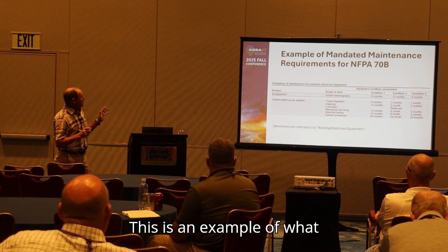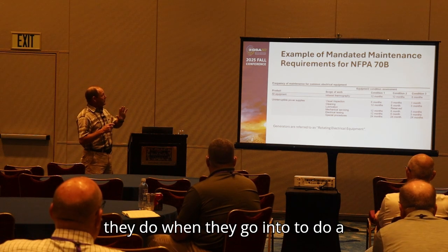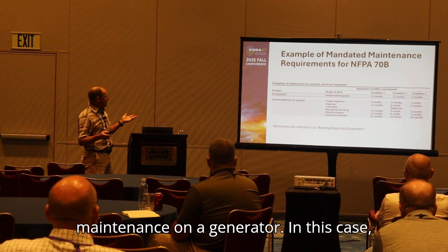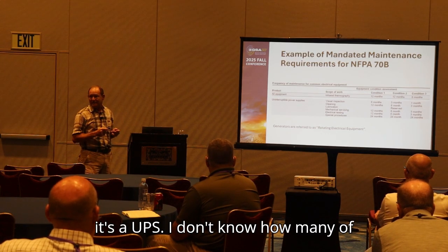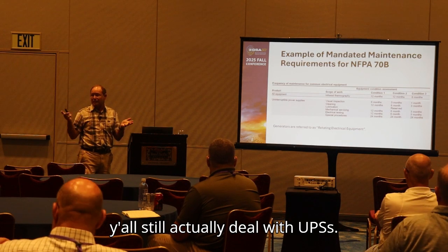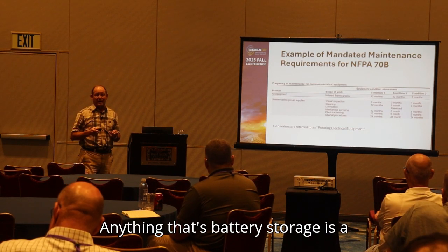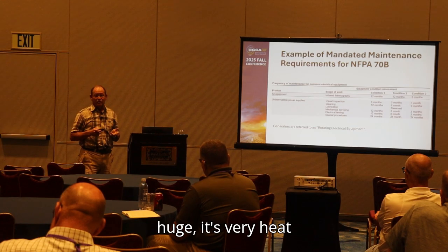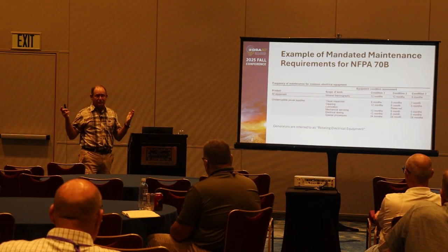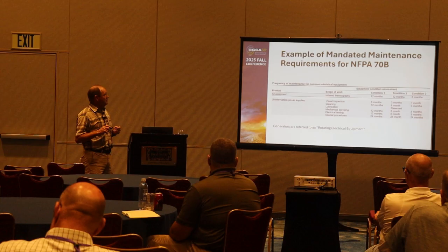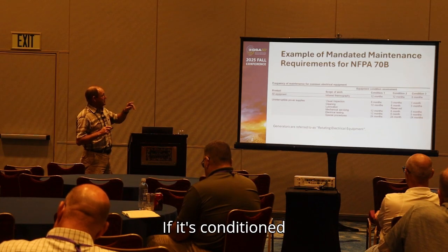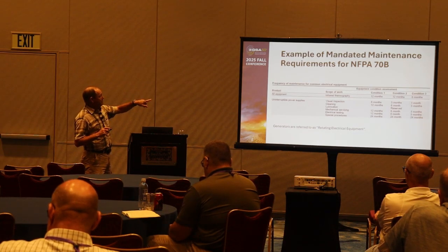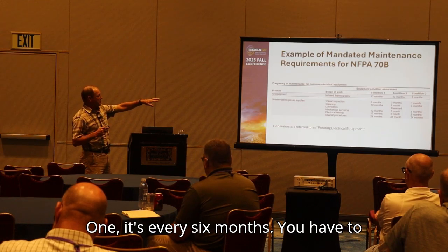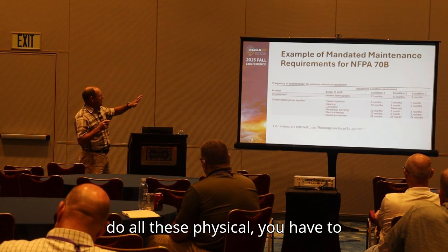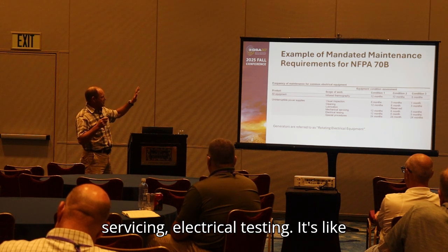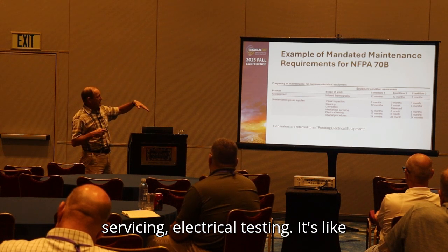This is an example of what they do when they go in to do a maintenance. On a generator, in this case, it's a UPS. I don't know how many of y'all still actually deal with UPSs. Anything that's battery storage is very heat-driven equipment. If it's condition 1, it's every 6 months. You have to do all these: physical, cleaning, lubrication, mechanical servicing, electrical testing. It's like once a year.